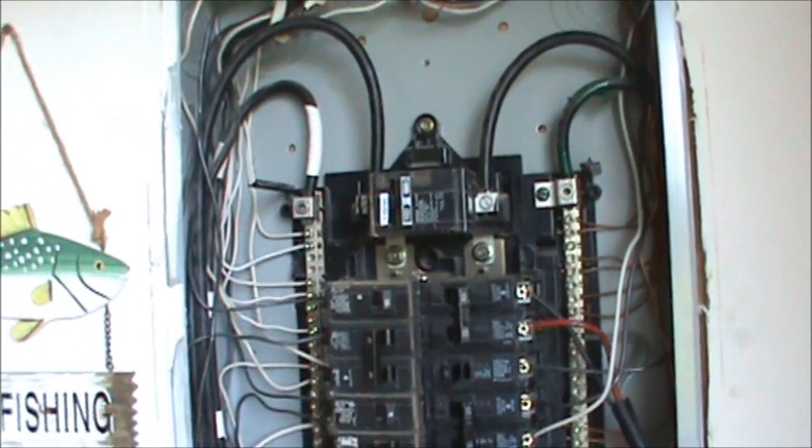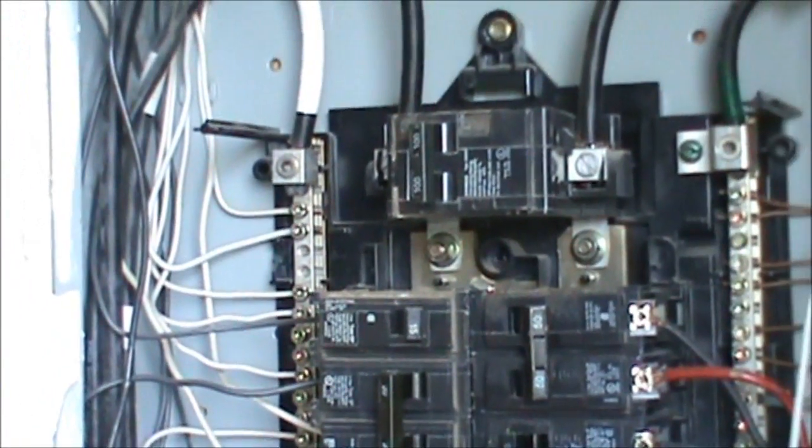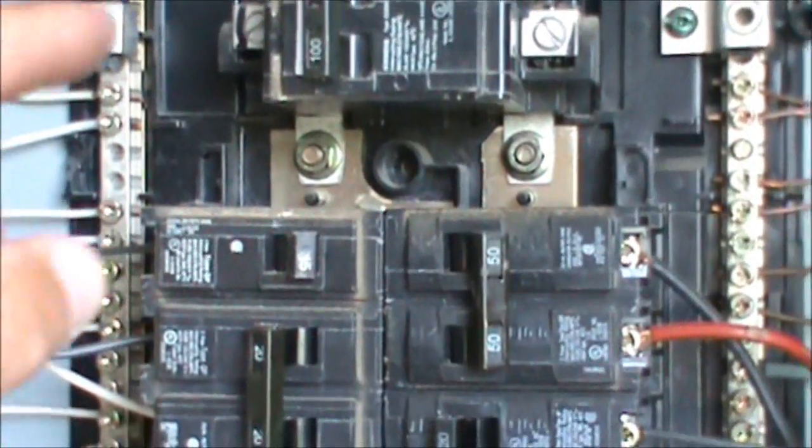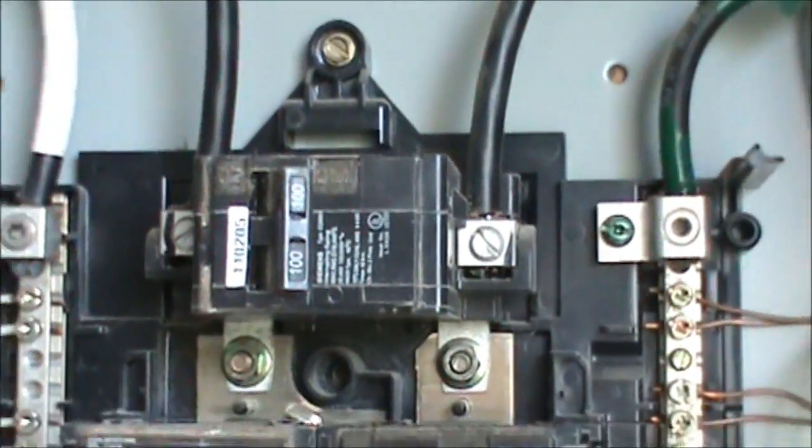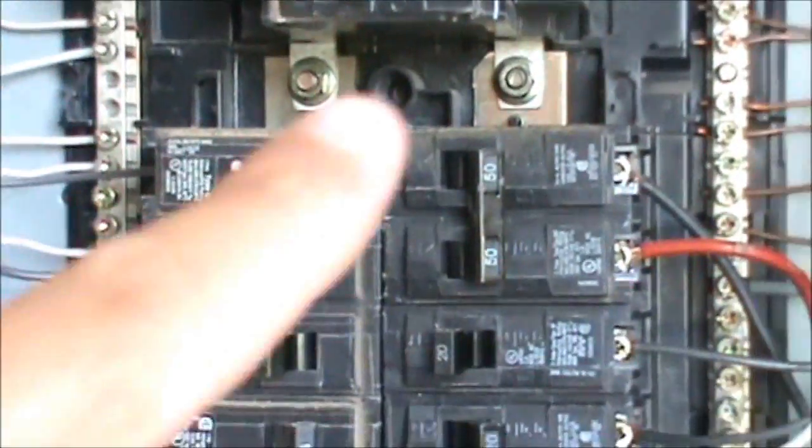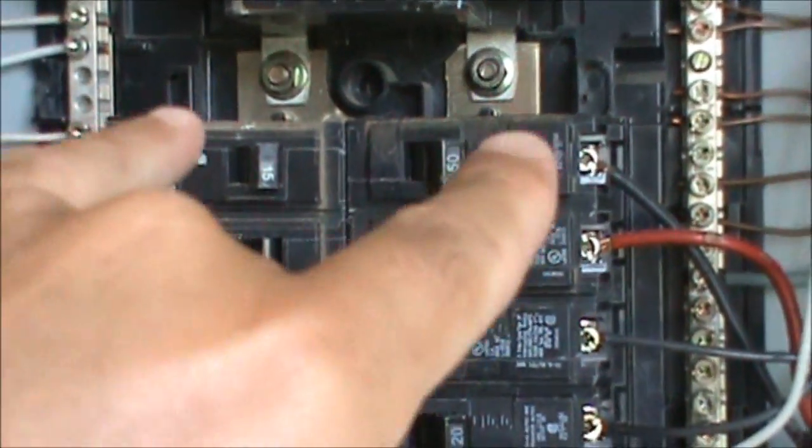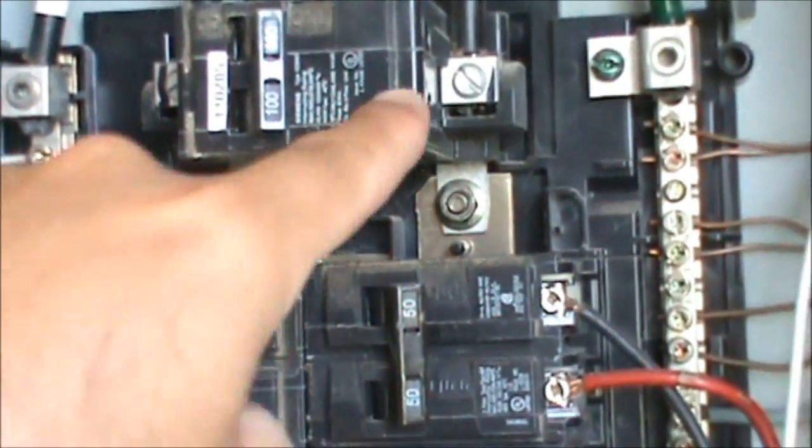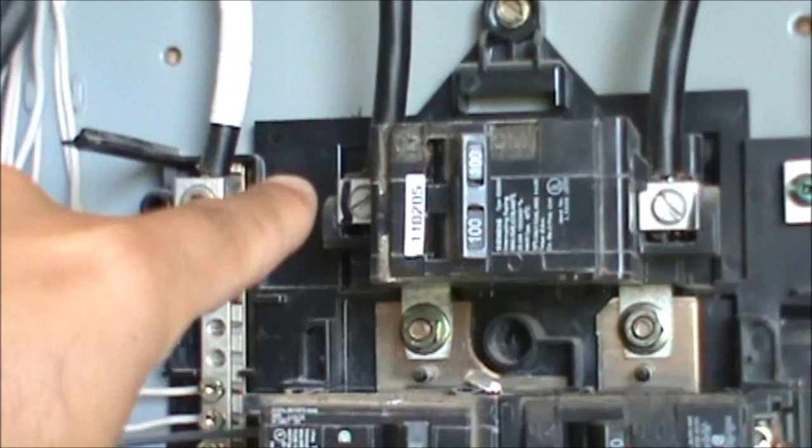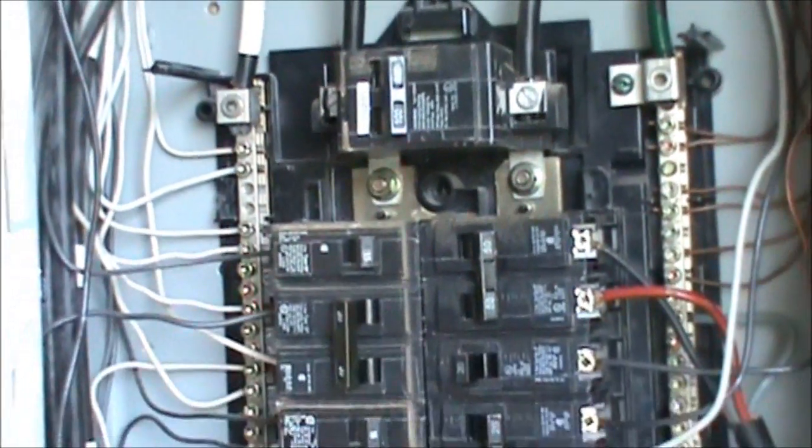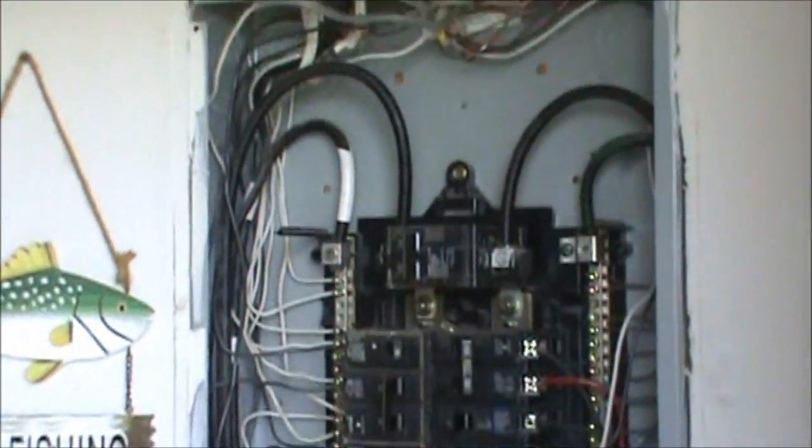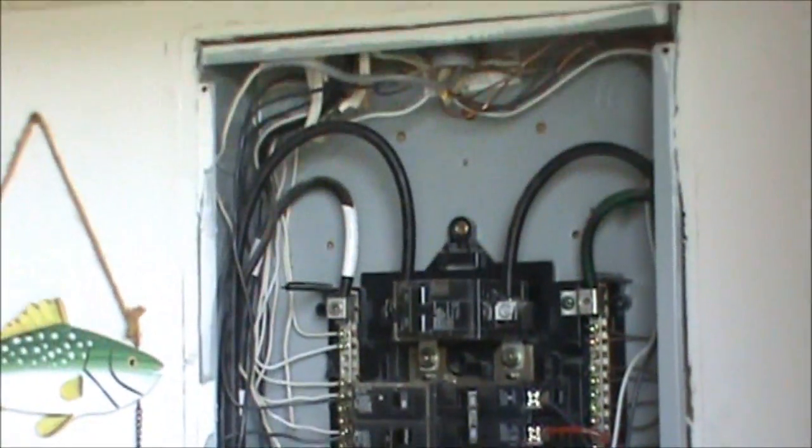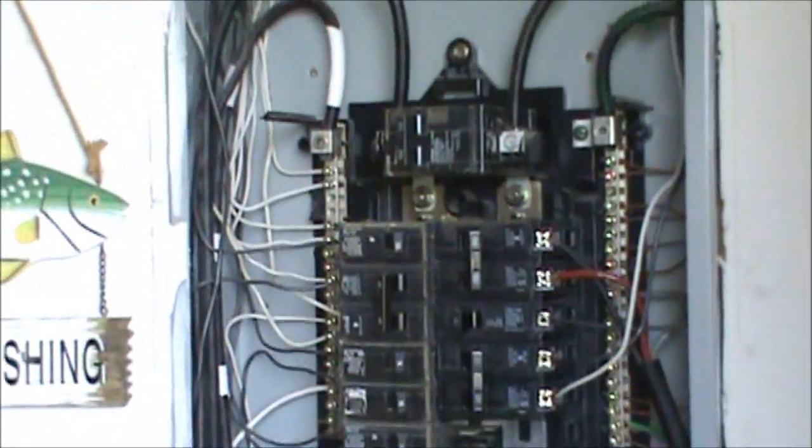When you're working on your panel, you want to turn off the main breaker. To do that, you're going to move this top breaker, 100 amp one, to the off position. Now the electrons aren't flowing through the rest of the board. However, these lugs here up top are still hot, so you have to be careful, you can't touch them. You might notice in my video mine is actually in the on position, and that is because I turned off the power on a separate building over here, so I can go into that breaker over there and that turns off all the power out here in my detached garage. Make sure that if you can't turn it completely off, you just turn it off at the breaker.